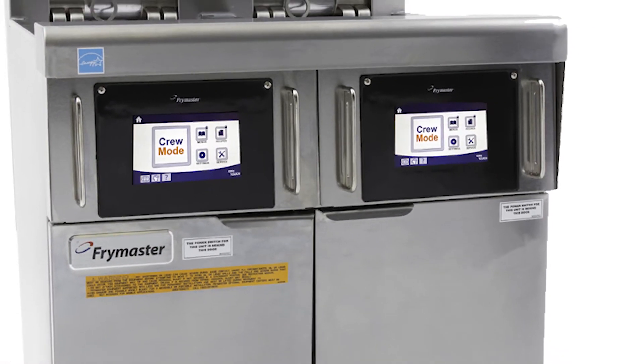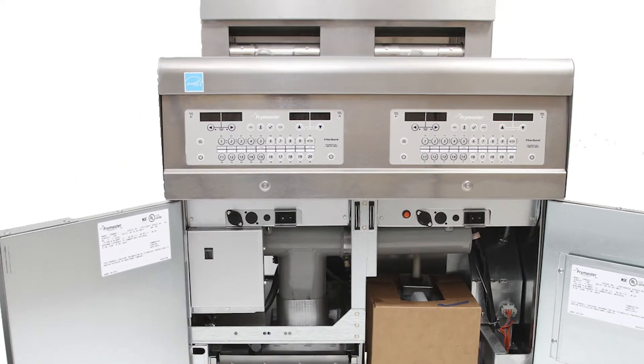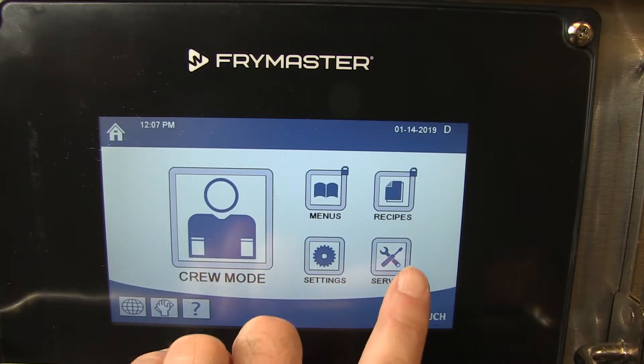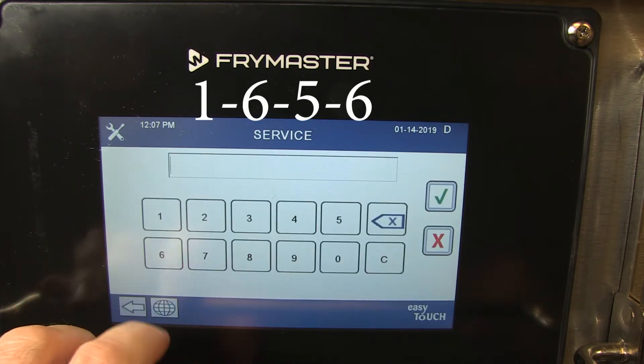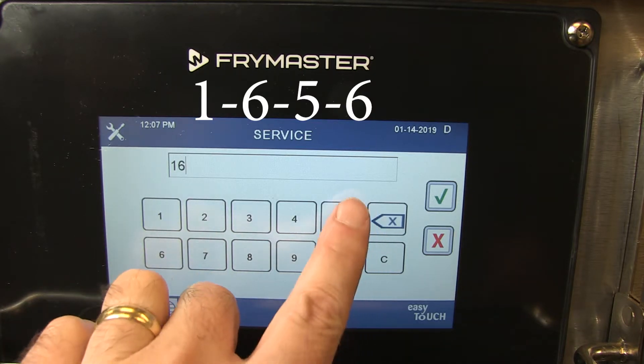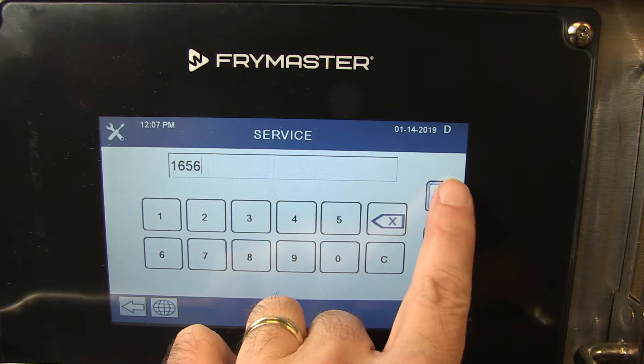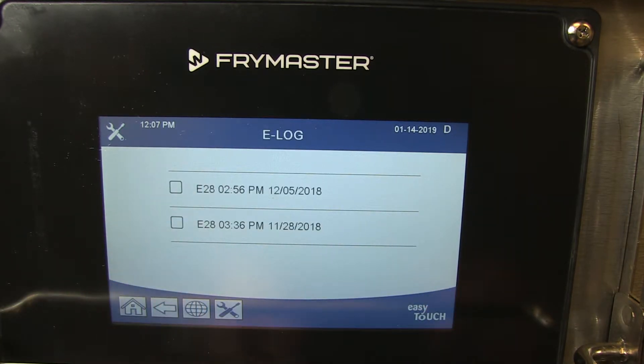Both the 4000 and 3000 platforms also record and display error codes. From the home screen on the 4000 series controller, tap the service icon, then tap the manager icon. Enter 1656 and tap the green check mark. Tap e-log, record the most recent error, and use the manual to decipher the code.